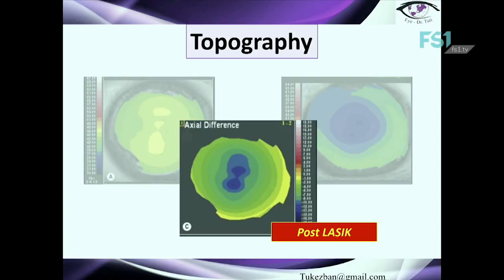Next, let's talk about the difference map. Here is a patient pre-operatively with oblique or with-the-rule corneal astigmatism visible on the pre-operative map. This is the same patient after LASIK surgery — the post-operative map. The device calculates the difference clearly between pre- and post-operative images and shows the characteristic of the toric ablation. So the difference map shows us the difference in curvature between measurements.